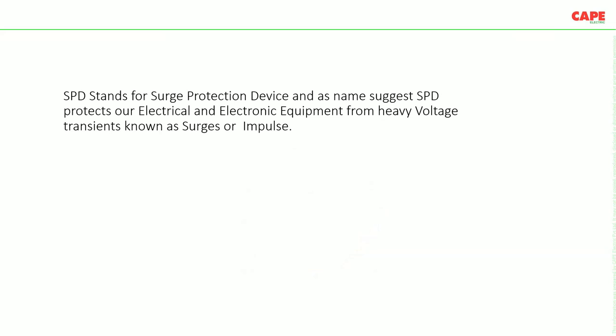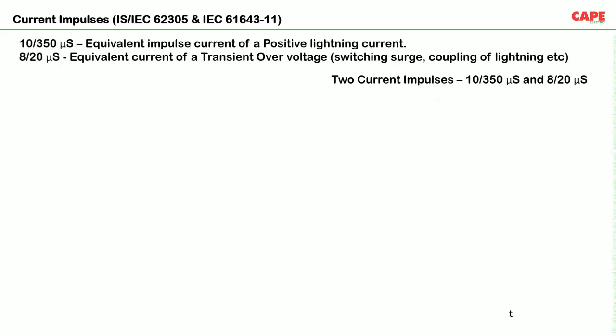So what is an SPD? SPD, as the name suggests, stands for surge protection device. It protects our electrical and electronics equipment from heavy voltage transients known as surges or impulses. Now, generally, lightning is going to strike and we don't know how it will be. So for the sake of testing and measurement, the standard has defined two types of current impulses. The first one is the 10 by 350 microsecond current impulse. The second one is the 8 by 20 microsecond current impulse. 10 by 350 microsecond is basically the equivalent impulse current of a positive lightning current. That means if we have to define a lightning impulse, it will be defined in terms of 10 by 350 microsecond, the positive lightning current.